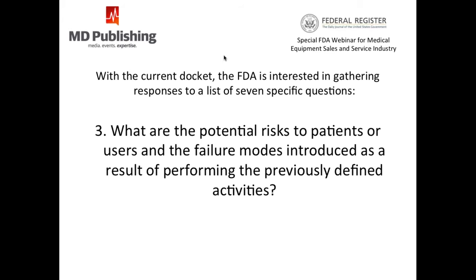Sure, this is Jonathan Gabe from ECRI. There are a range of risks and failure modes for the immense range of devices out there. The least risky are failures detected via self-diagnosis by the device, usually at startup, or the mode may be quite visible to the operator, or the failure mode may not result in patient harm. The most risky failures are those that are not evident and can deliver harm. And let's remember that having the device out of service is in itself a risk.